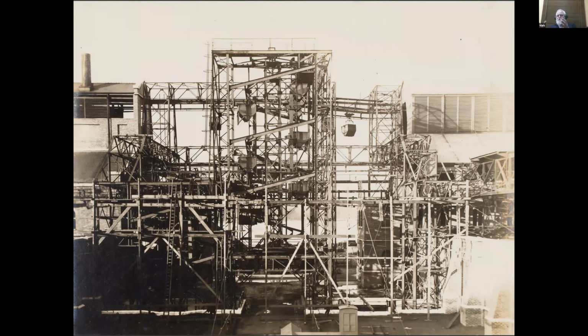It's a monorail system, so it's divided into electrically separated sections of track. So as a Telpher truck passes on to a new section of track, the block section of track behind it is electrically isolated. And then when that Telpher truck reaches the next one, the power is restored. So if you've got 3 blocks A, B, C, as it goes from A to B, the power is isolated to A. Then when it goes from B to C, the power is restored to A, but the power is then isolated to B. And that's designed so that you can't have the problem of a Telpher truck running up the backside of another one, that they're always separated by a block.